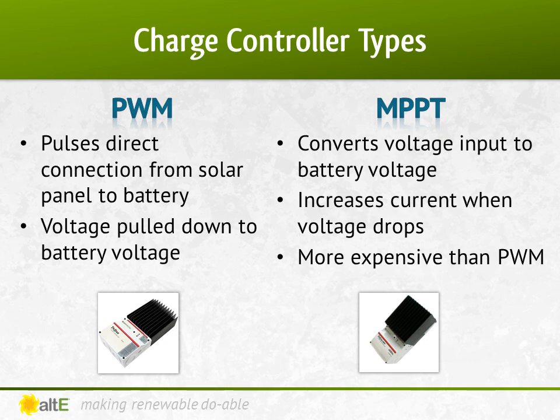MPPT charge controllers measure the VMP voltage of the panel and then down-convert the PV voltage to the battery voltage. Because power in equals power out, when the voltage is dropped to match the battery bank, the current is raised, so you are using more of the available power from the panel.